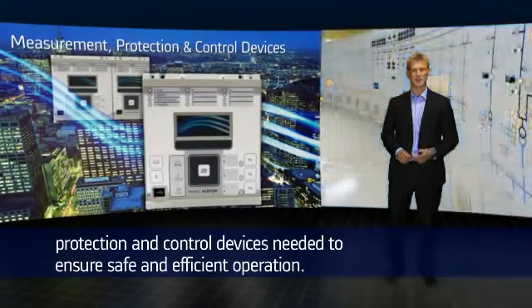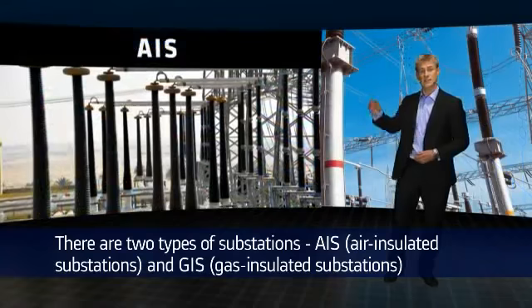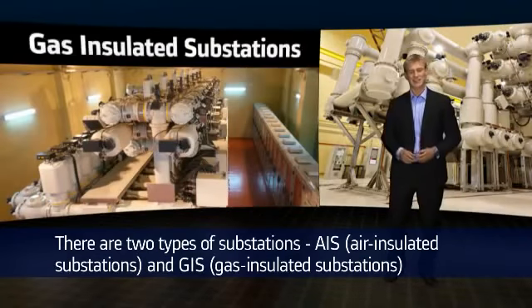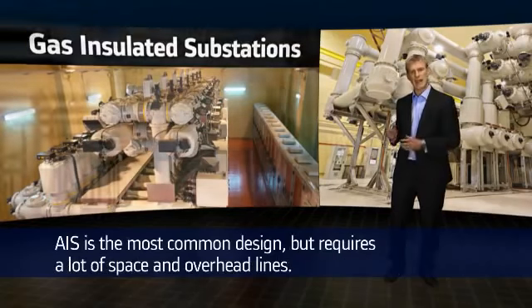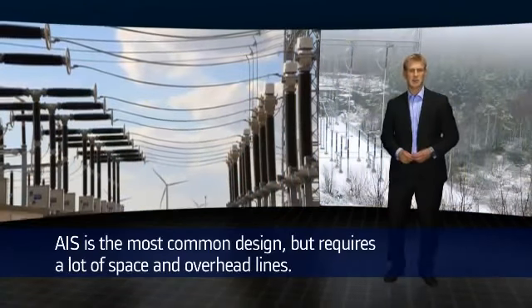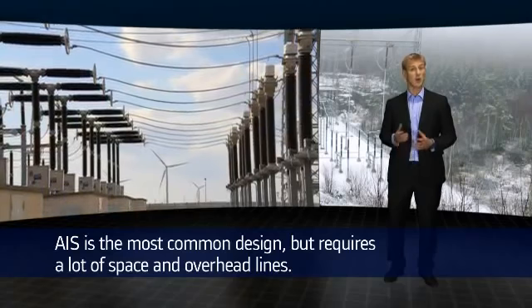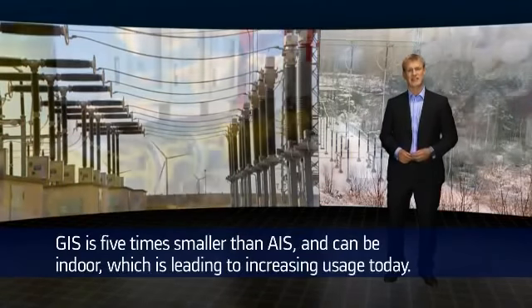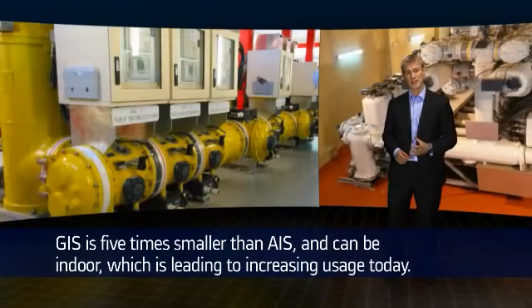There are two types of substation: AIS, air-insulated substations, and GIS, gas-insulated substations. AIS is the most common design but requires a lot of space and overhead lines. GIS is five times smaller than AIS and can be indoor, which is leading to increasing usage today.